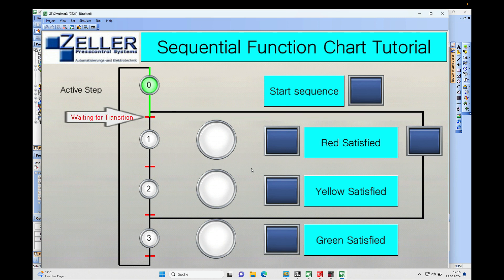A Sequential Function Chart works like a step-by-step executed program where you have steps, which you can see right here, and every step is forwarded by the satisfaction of a transition, which you can see right here. Then it will start the next step, and so on — step by step — using a transition where we check that a step is satisfied.